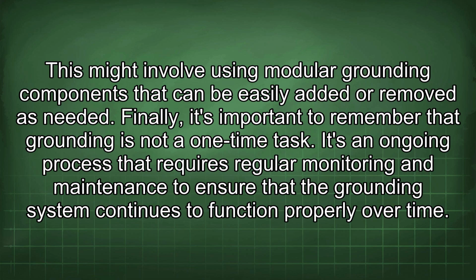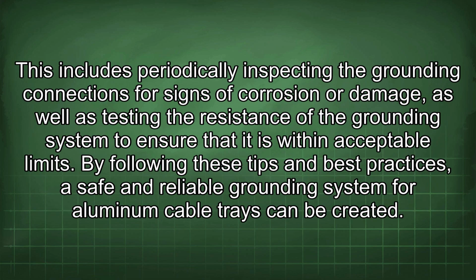Finally, it's important to remember that grounding is not a one-time task. It's an ongoing process that requires regular monitoring and maintenance to ensure that the grounding system continues to function properly over time. This includes periodically inspecting the grounding connections for signs of corrosion or damage, as well as testing the resistance of the grounding system to ensure that it is within acceptable limits. By following these tips and best practices, a safe and reliable grounding system for aluminum cable trays can be created.